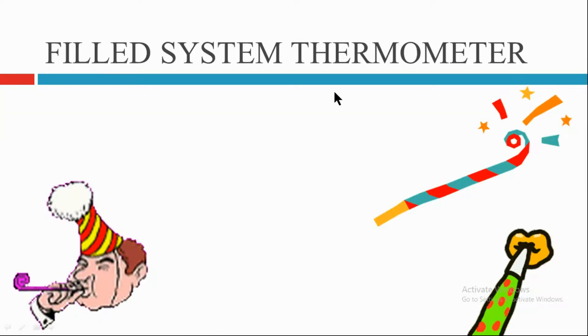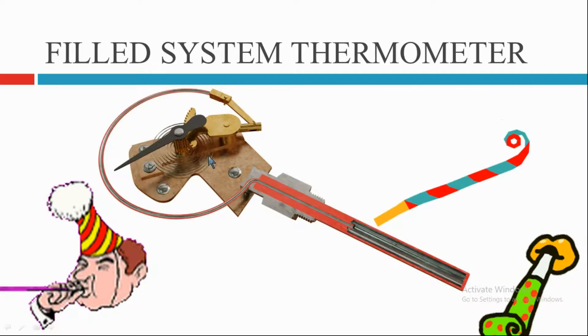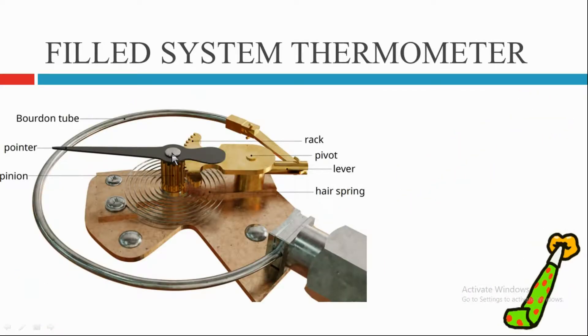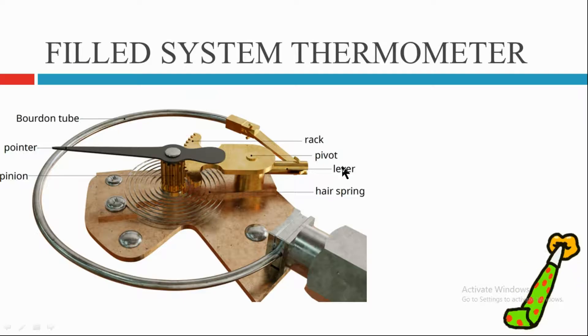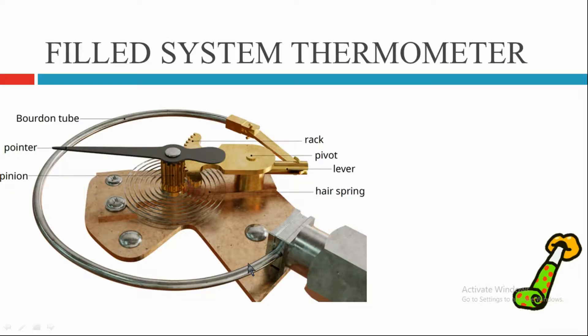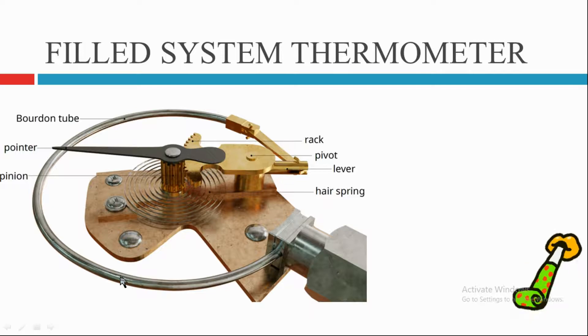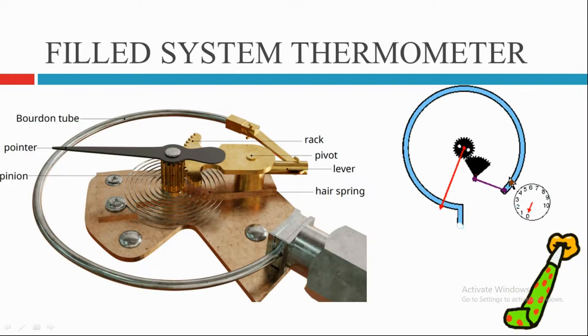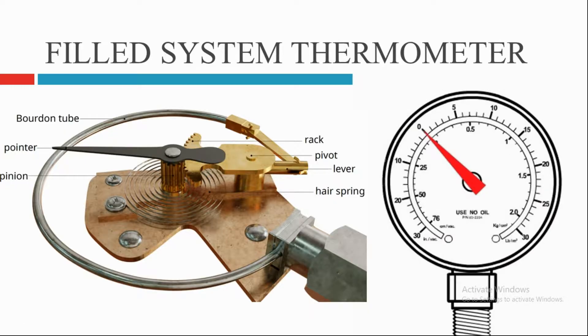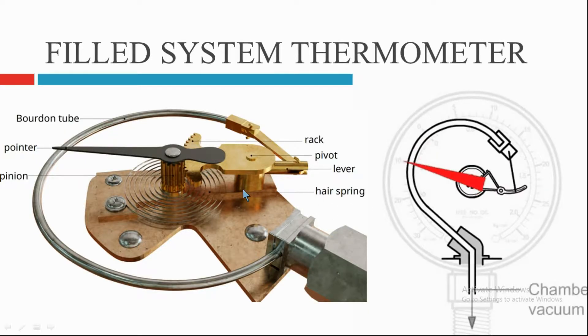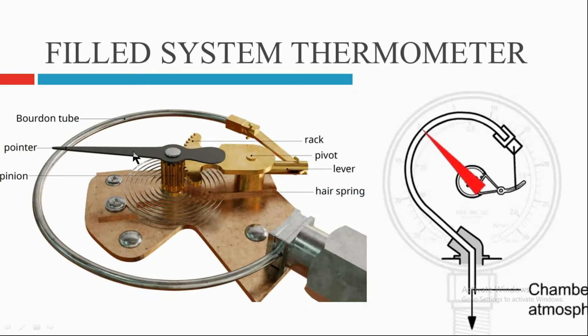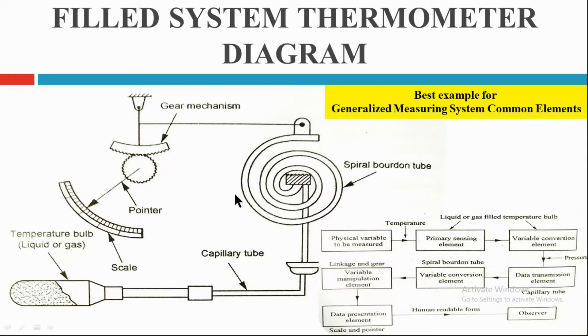Let's see the various measuring system elements in a filled system thermometer. Looking at the internal parts: there is a pointer connected with a pinion, which is in contact with a rack. The rack is actuated with the help of a lever mechanism, which gets its power from the Bourdon tube. Inside the Bourdon tube, a pressurized fluid is already filled. If the pressure increases, the Bourdon tube expands; if the pressure reduces, it shrinks — like a party whistle. A thin hairspring is also attached at the pinion gear, which retracts the pointer under no-load conditions.